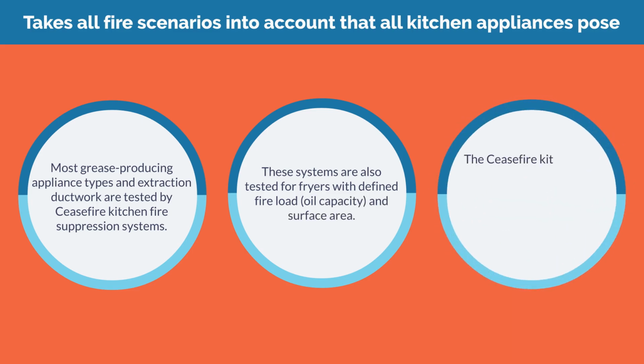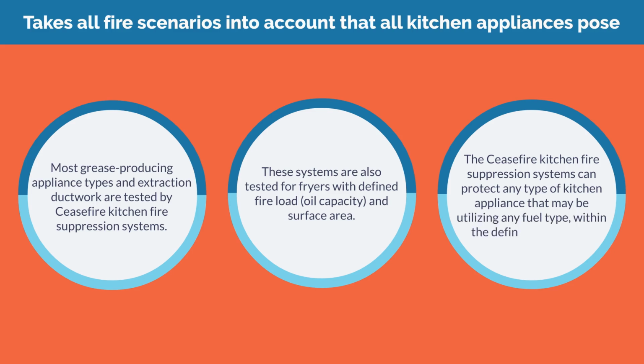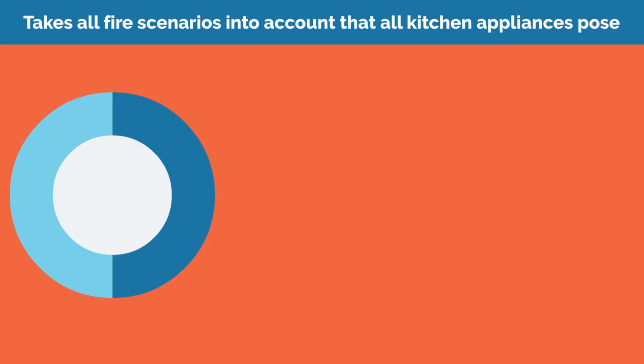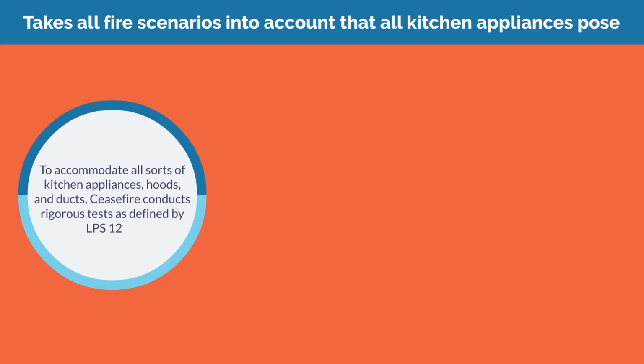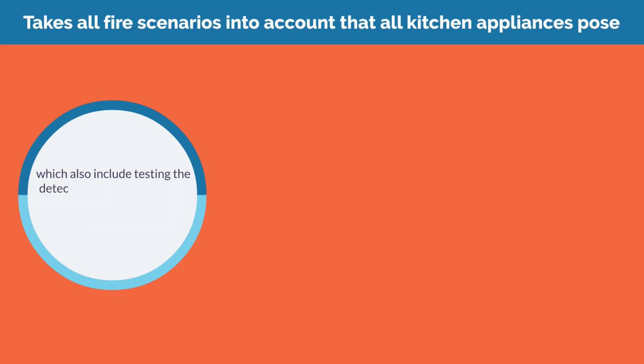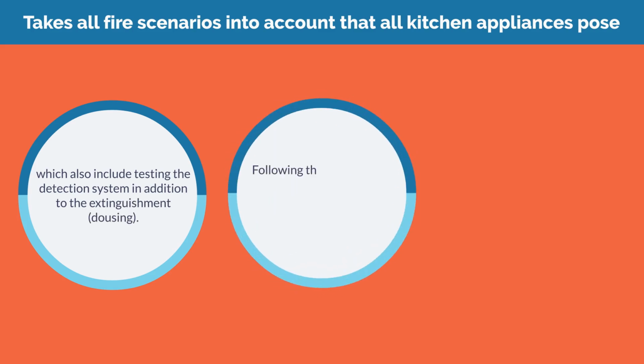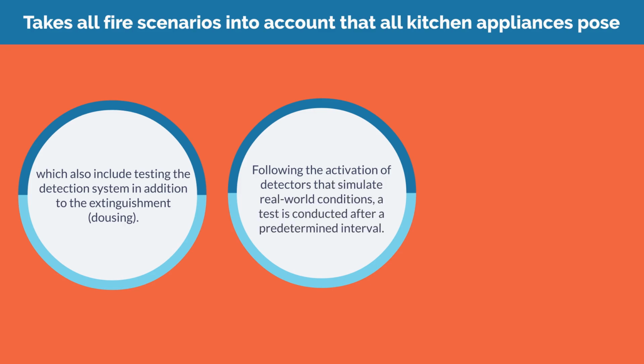The Ceasefire kitchen fire suppression systems can protect any type of kitchen appliance that may be utilizing any fuel type, within the defined limitations. To accommodate all sorts of kitchen appliances, hoods, and ducts, Ceasefire conducts rigorous tests as defined by LPS 1223, which also include testing the detection system in addition to the extinguishment. Following the activation of detectors that simulate real-world conditions, a test is conducted after a predetermined interval.